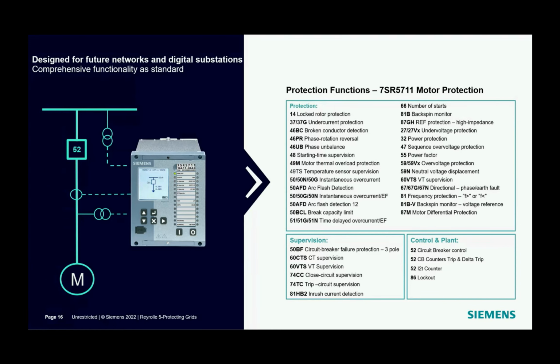So with the addition of the voltage inputs, the device has all the associated protection functions. 27 undervoltage protection can be used to disconnect the motor in the event of a low terminal voltage. And as a frequency measure, 81B backspin monitor function makes sure the attempted starting of the motor is inhibited until after the motor has completely stopped.